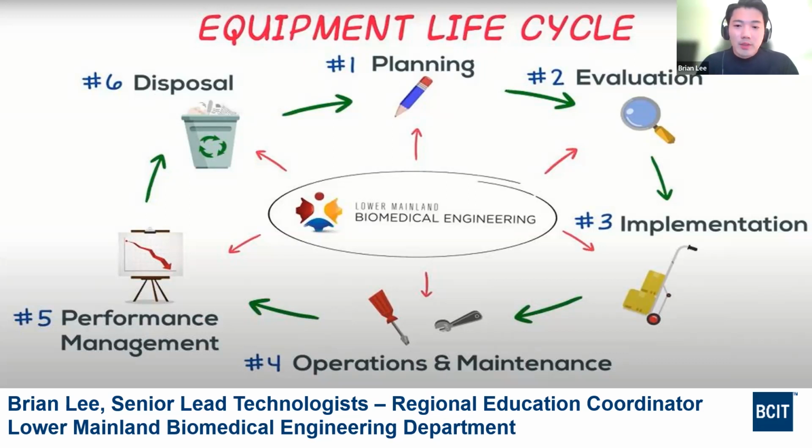What that means is we investigate any incidents that happen to the patients or could possibly happen to the patients. And we also conduct upgrades and updates in order to keep the medical devices up to date, for example, for cybersecurity or any patient or customer needs that they are asking for. And when the time comes, our medical devices get old and they get buggy, of course. So we are also involved in decommissioning and disposal of medical devices.